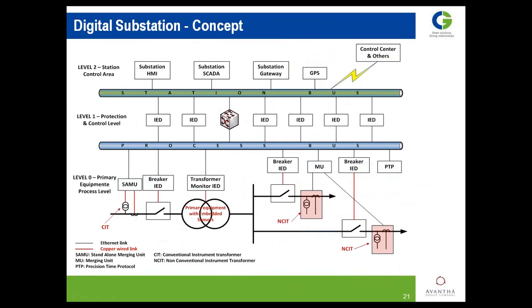I'll not go more deep on that, but basically it is like that. I have 5 more minutes, so I'll cover by the time. Basically it is a substation with more towards level 0, the primary equipment or process level intelligence, and the same is getting reflected to the protection and control level and the station's control area. And here the focus is more in this domain. Can I have conventional or non-conventional equipment? Can all the equipment be intelligent and getting monitored and controlled so that the life is getting estimated, the fault is getting predicted, and the system is working healthy 24/7 and 365 days without a source of problem in my system?